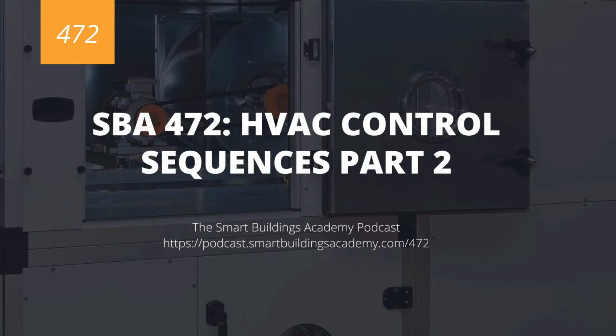Now, that's typically in fan coils and rooftops. In air handling systems like air handlers, especially VAV air handlers, the air will be delivered via the ductwork to a VAV box, which then will regulate it even more. Now, we're going to come back to that because there are some important things that have to happen in order for that to work. But before we do that, let's go through a fan coil.